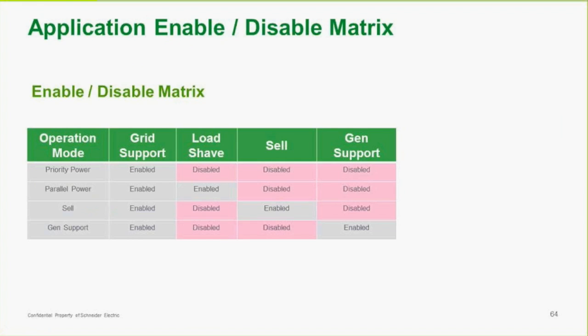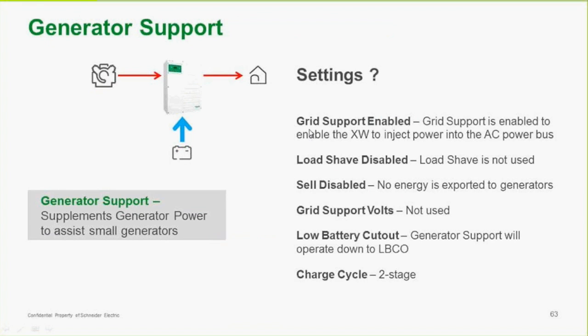Generator support. So grid support is enabled. We have load shave disabled. We don't have a grid attached to it. Sell is disabled. Grid support volts is not used. We're going to use the low battery cutout, and the charge cycle is 2-stage. So now we have support for our gen set.